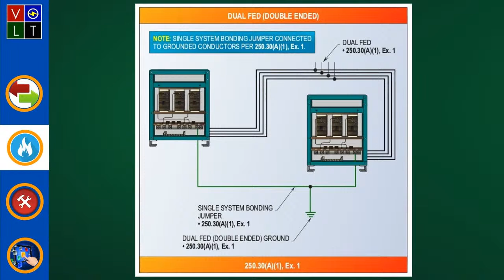Yeah, no worries. All right, now this is where you have an additional system bonding jumper, and what they tell you here is that you can have an additional system bonding jumper connection. Basically, that means there's going to be more than one. And this is permitted to be made, and let's say I will say this, it's only permitted to be made if doing so will not create what? A parallel path. Yeah, 250.6. And that parallel path is for the grounded circuit conductor. And this additional system bonding jumper shall not be permitted to be smaller than the other system bonding jumper, but it shall not be required to be larger than what? The ungrounded phase conductors. Yep.